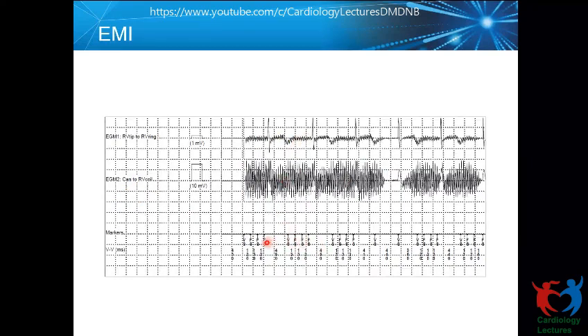So if this patient was pacemaker dependent, because of continuous oversensing, the pacemaker would not pace, which is the possibility. So in this case, there's nothing that you can do by the settings of the pacemaker. We should help the patient identify the source of electromagnetic interference and avoid it if it is from a home or office related source. But this might happen in the hospital, where your surgeon is likely to operate on a pacemaker implanted patient with an electrocautery, and that's why we typically program the pacemaker to VOO mode. Or you recommend the surgeon use a bipolar cautery when the operation is significantly away from the pacemaker system itself.